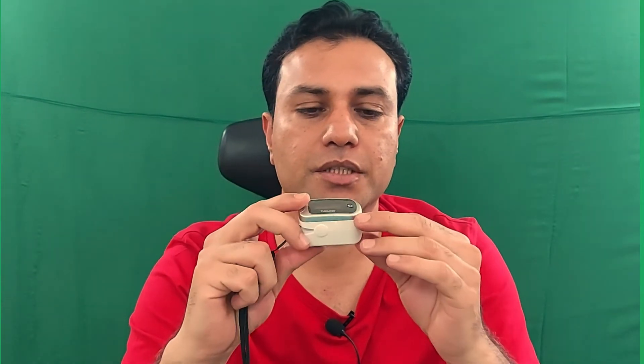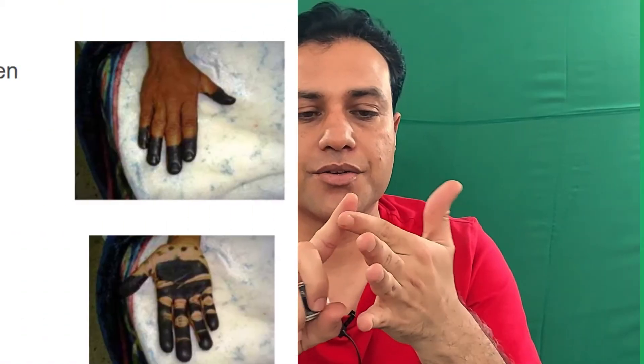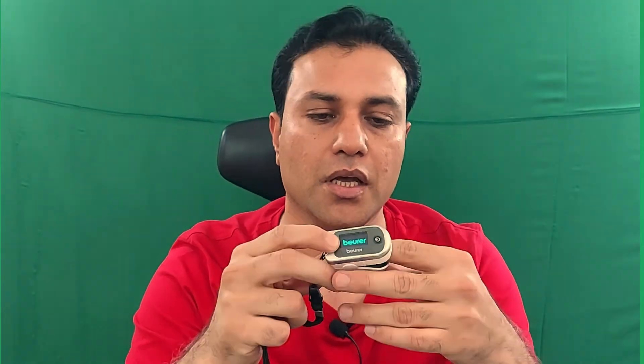Now let me explain the limitations of this device. If there is color on your nails, henna, or any other color on your finger, that will affect the blood oxygen saturation result. The best method is to remove any color or varnish from the nail and wash your finger with normal water — not hot or cold water — as that will also affect the oxygen saturation result.